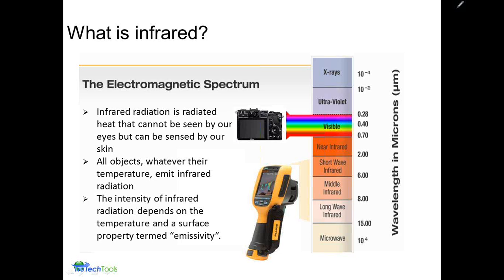One of the key ingredients in that is the term emissivity. It's the reflective properties of the material. When you go through a thermography infrared class, that is one of the key subjects talked about at some length, because understanding it is very important in the interpretation and analysis of your image. One of the areas we're primarily concerned about in the building envelope is the long wave, typically between 8 and 14, or in this case 8 to 15 micron. It's the wavelengths that are most appropriate for imagery in the building envelope area.